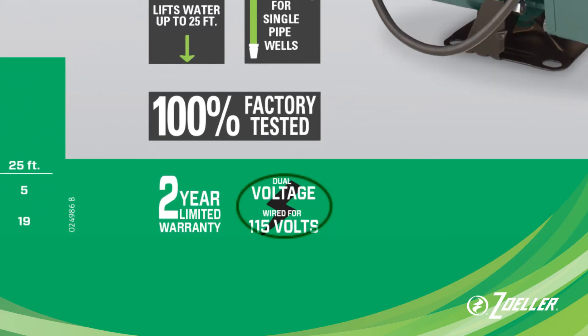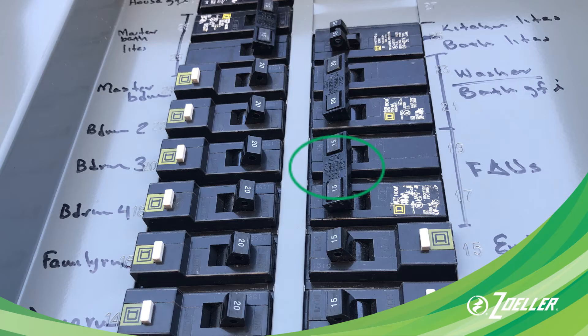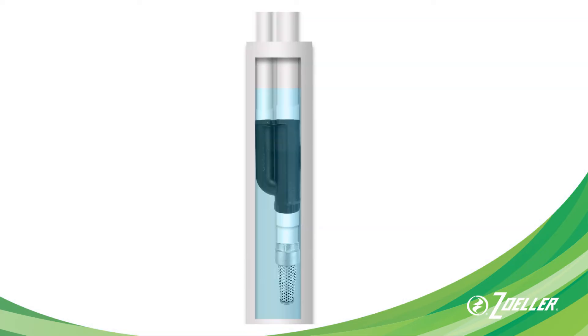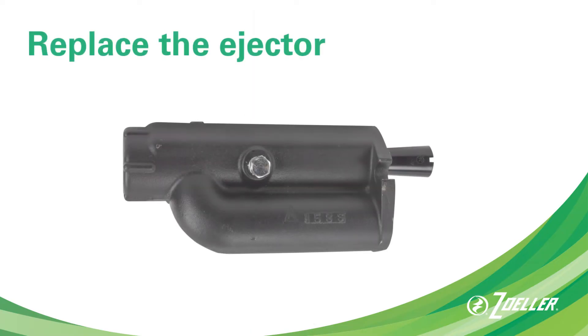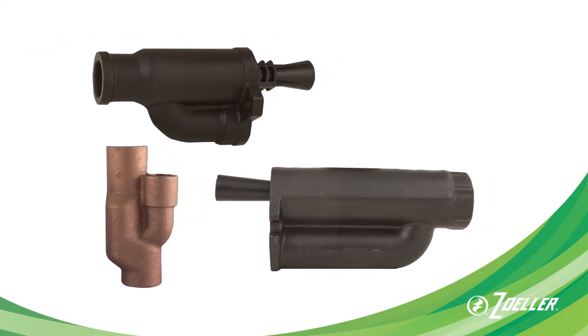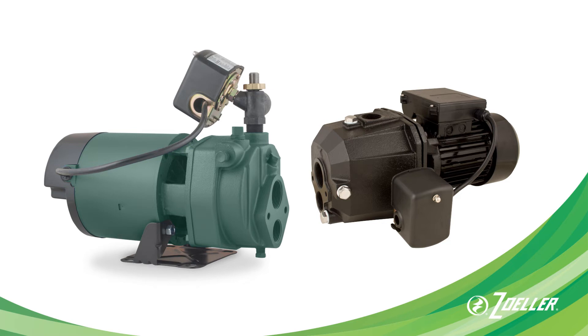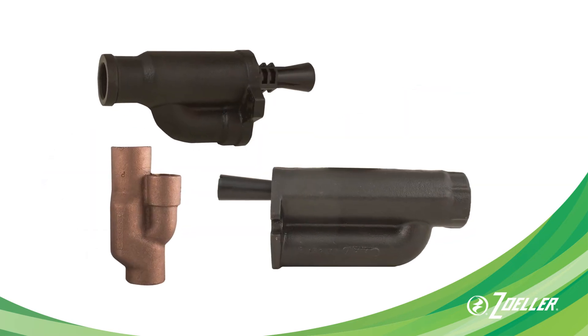Zoeller jet pumps are dual voltage — you can convert your pump to either 115 or 230 volts to match your electrical requirements. If you're replacing a convertible pump that has an ejector in the well, you'll also need to replace that ejector. This is always a good idea because every ejector is designed to work with a specific pump model and manufacturer, and the ejector that's been in the well may be worn out.